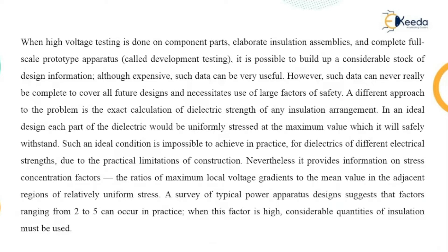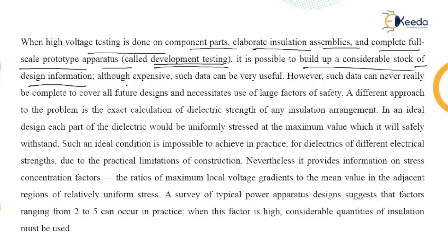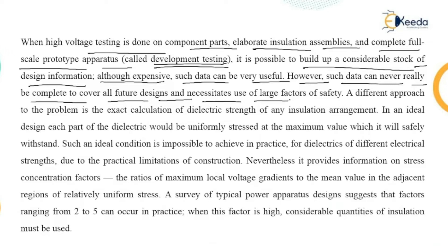High voltage testing is done on component parts, elaborate insulation assemblies, and complete full-scale prototype apparatus — called development testing. It is possible to build up a considerable stock of design information this way. Although it is expensive, such data is very useful. However, such data can never really be complete to cover all future designs and necessitates the use of large factors of safety.